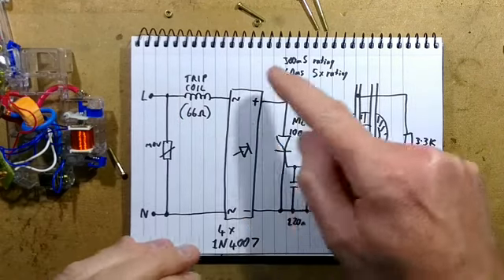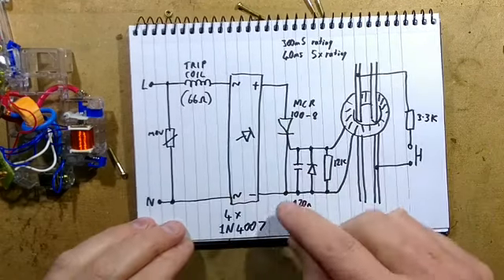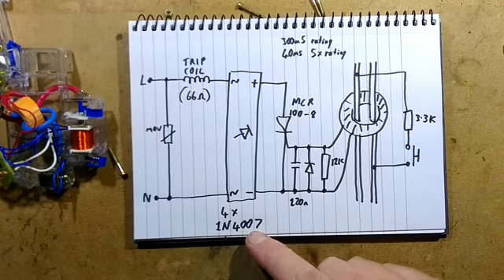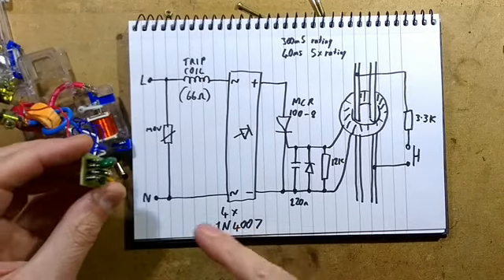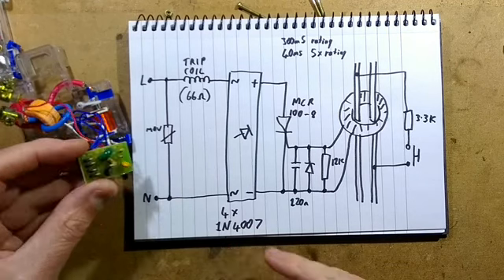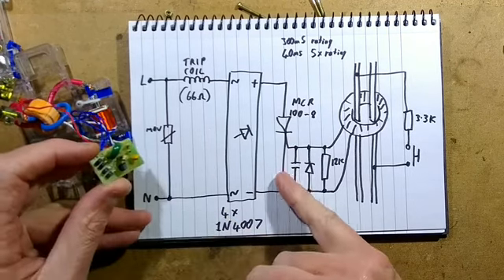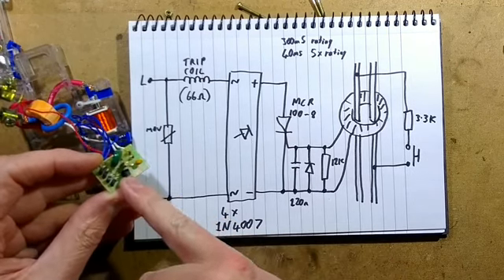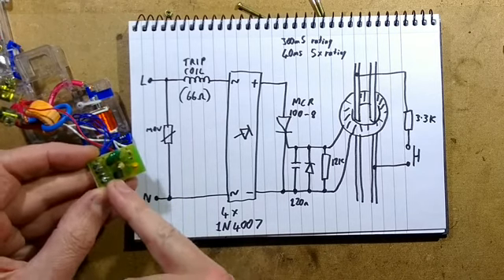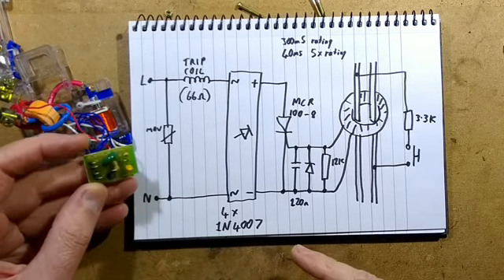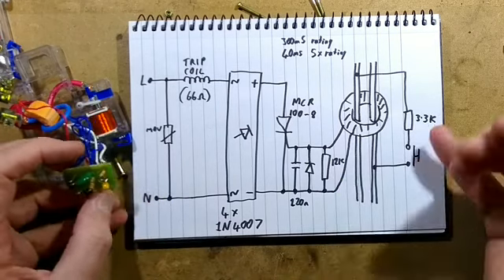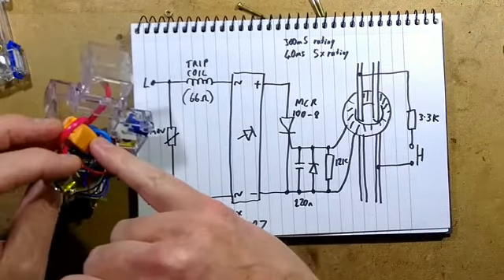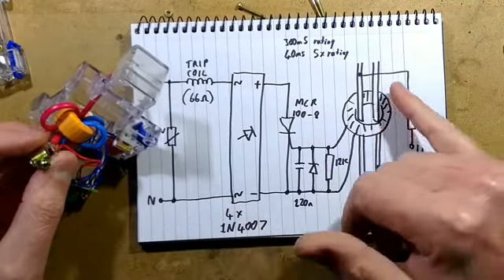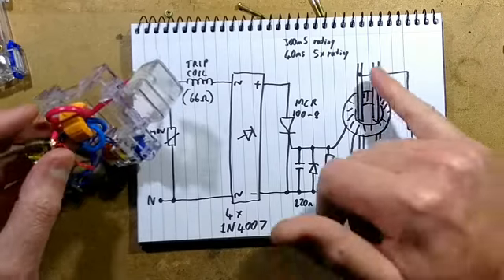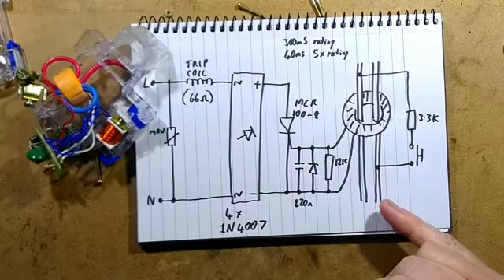It goes through a trip coil, then through a bridge rectifier made from 4 discrete 1N4007 diodes, 1 amp diodes, just conventional ones. That's these 4 diodes here. And then it goes to a thyristor, a super sensitive gate thyristor, an MCR100-8, very common. And after that, it's the sense coil here, which has the phase conductors. I've shown them going through it once, but they actually go through twice for extra oomph.